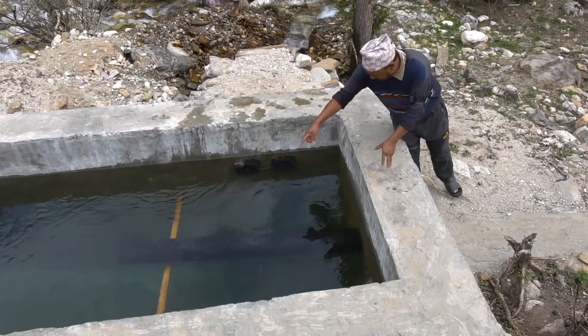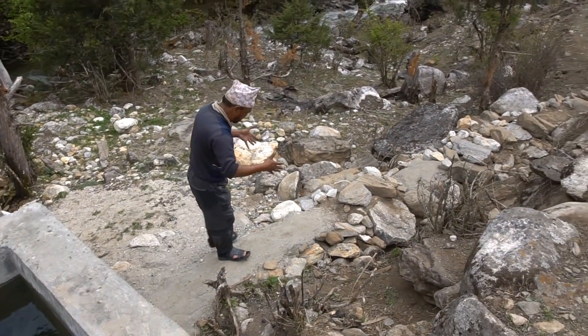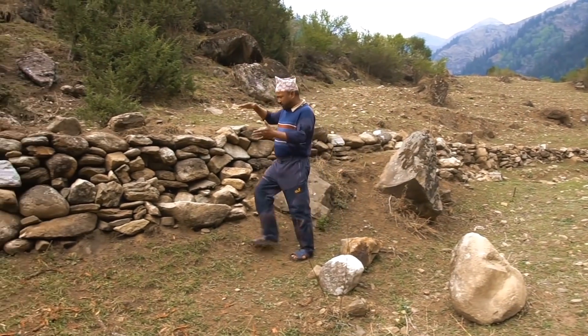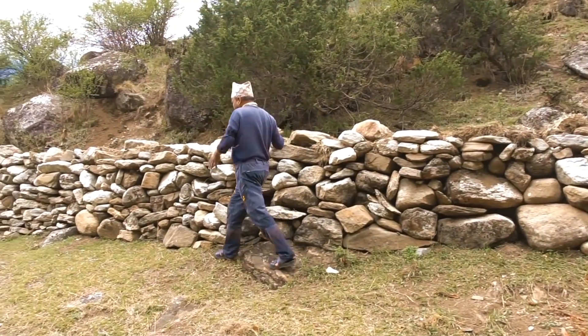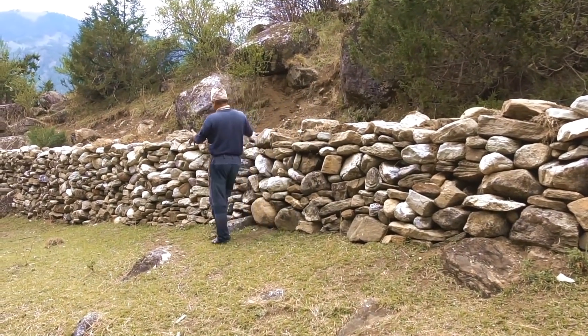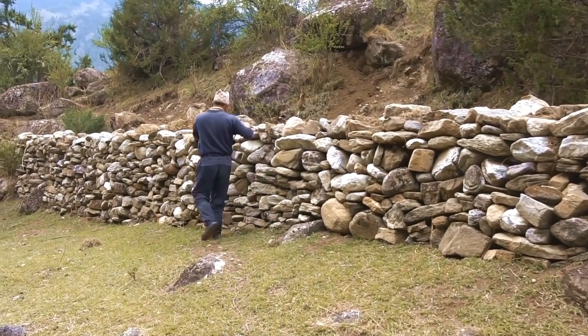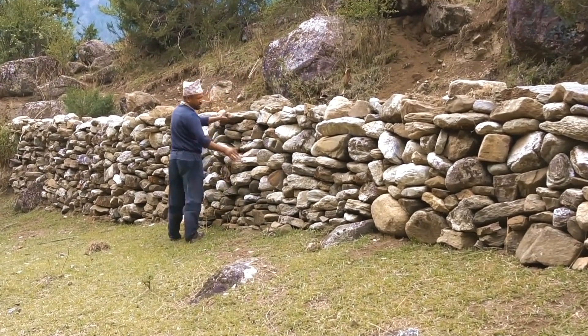From this 2 meter long, 200 millimeter diameter HDPE filter intake pipe, the water flows inside the 490 meter long penstock down to the turbine house. The land and ground level is hardly ever straight — it goes up and down. So when needed, we either dig into the ground or build up a stone wall to position the 490 meter long HDPE penstock pipe, making sure the pipes are safe and the water inside the penstock flows at a steady slope down to the turbine house.